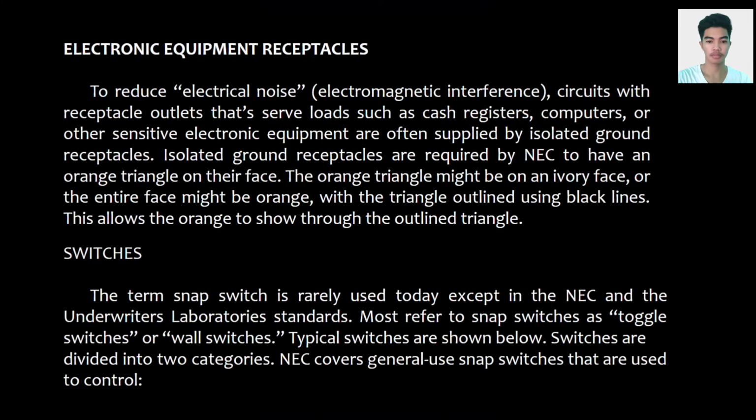What is electronic equipment receptacles? To reduce electrical noise, electromagnetic interference, circuits with receptacle outlets that serve loads such as cash registers, computers, or other sensitive electronic equipment are often supplied by isolated ground receptacles.